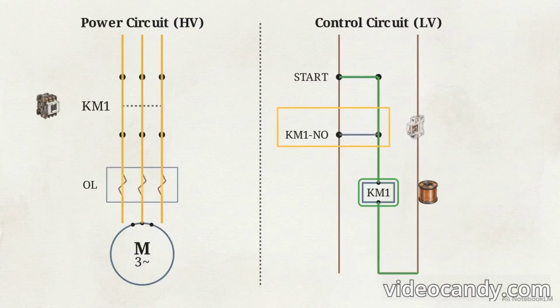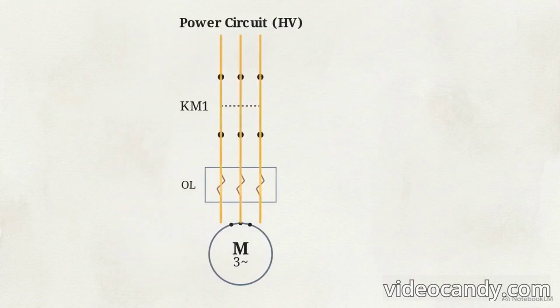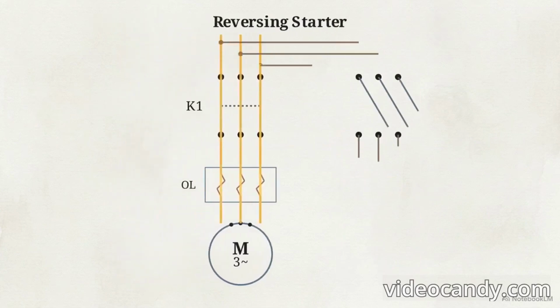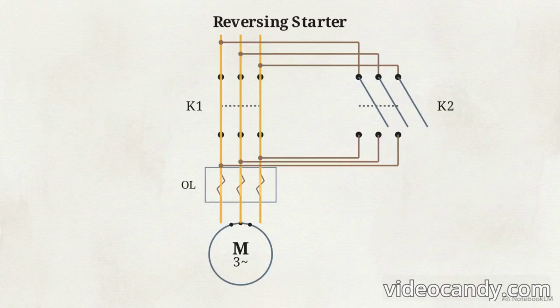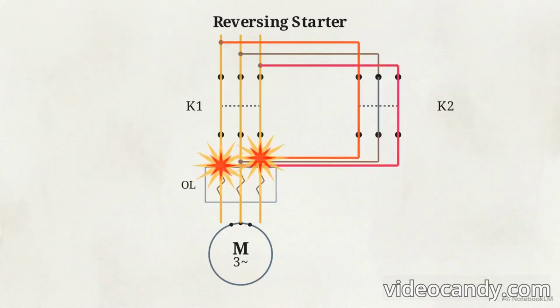On the control side, pressing the physical start button completes the low-voltage loop, energizing the contactor coil and snapping the main contacts closed. To keep the motor running after the operator's finger leaves the button, a normally open auxiliary contact is wired in parallel. As the main armature closes, this auxiliary contact closes alongside it, latching the control circuit and keeping the coil energized.